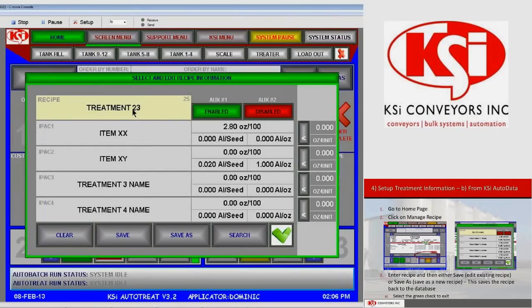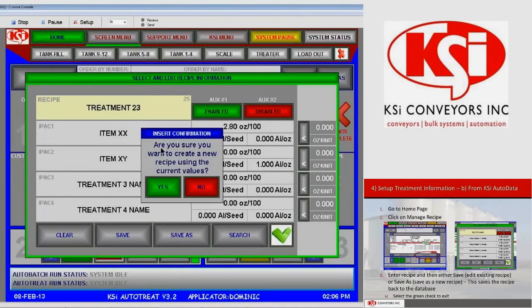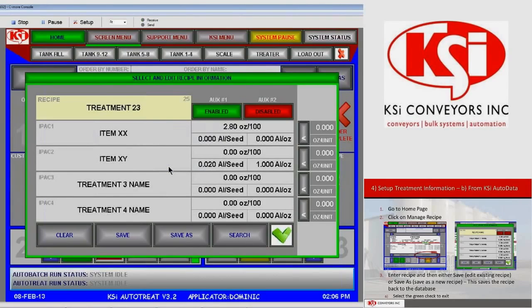Once we have this recipe in here, we want to do a save as. Save as creates this as a new item, or a new recipe, I should say, in the database. We don't want to do a save because that would overwrite the recipe that we loaded. So we want to do a save as. We do save as, and it says, are you sure you want to create a new recipe using the current values? We say yes, and it's going to add this recipe into the database.